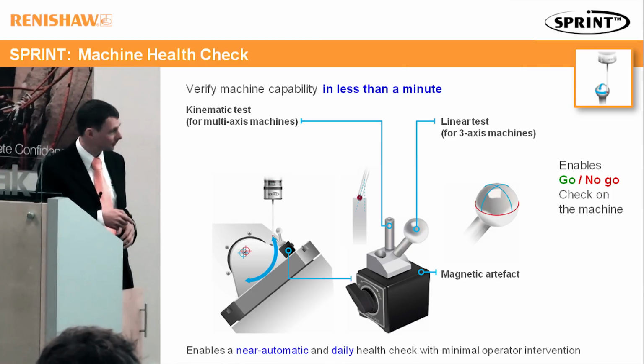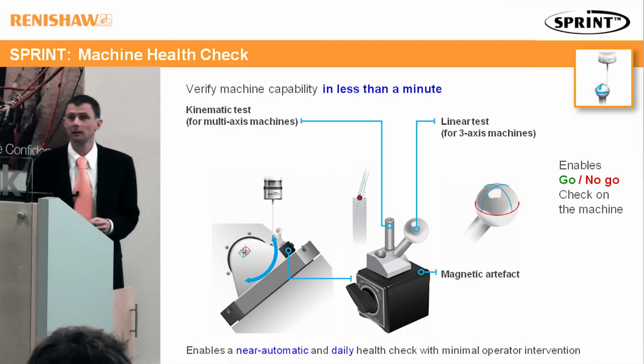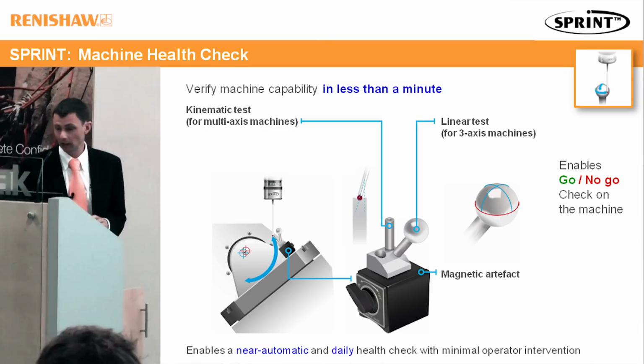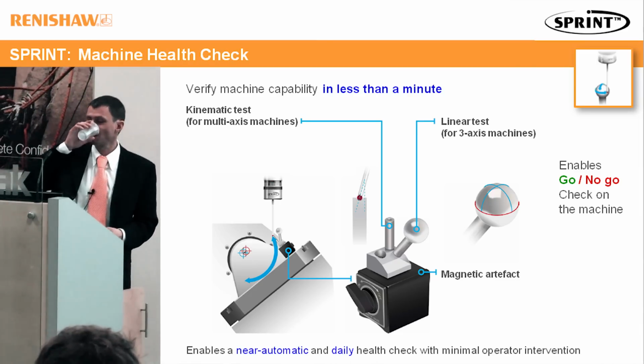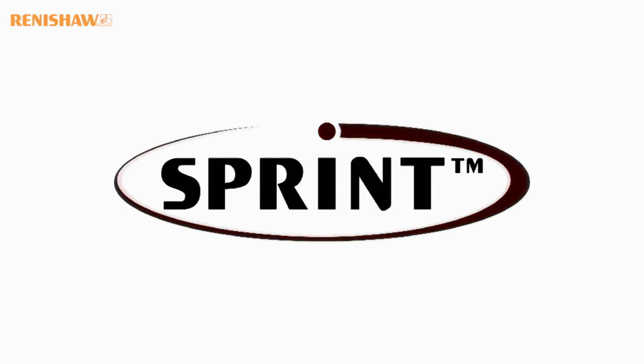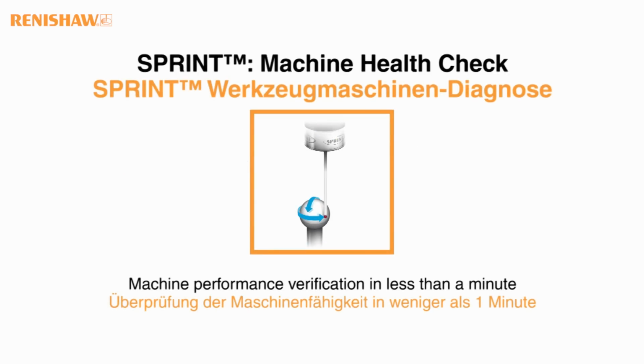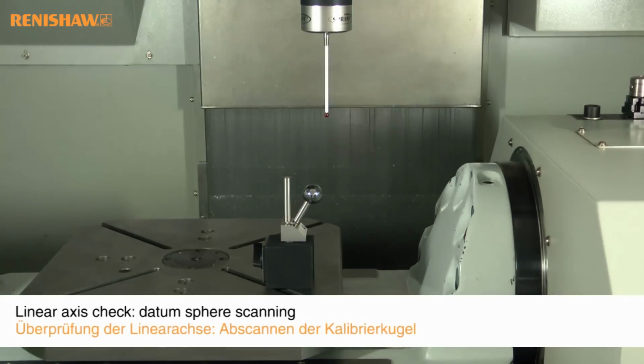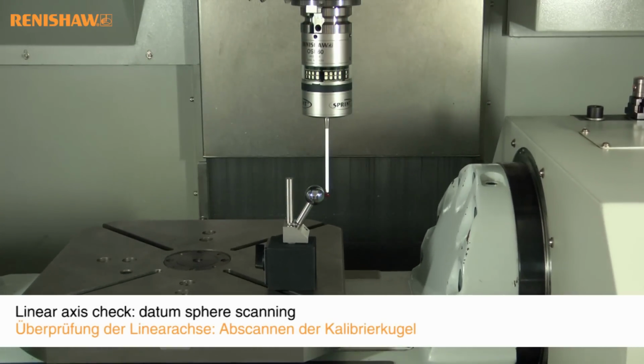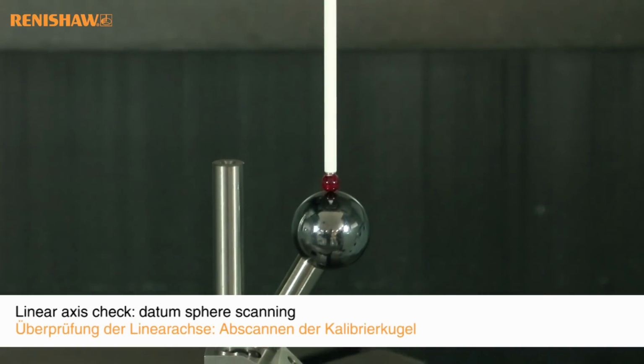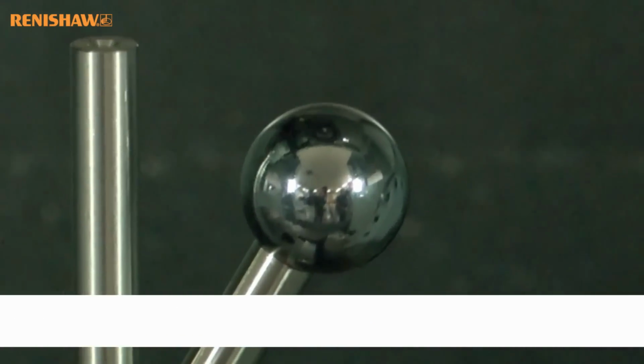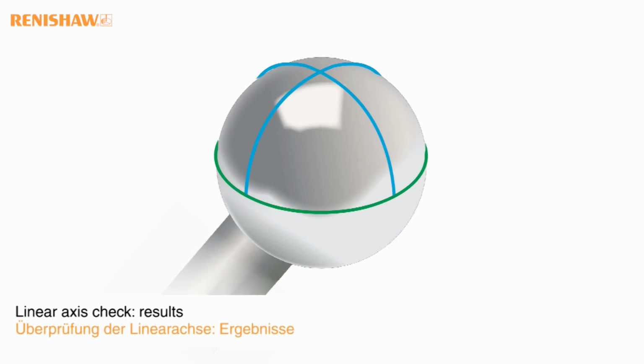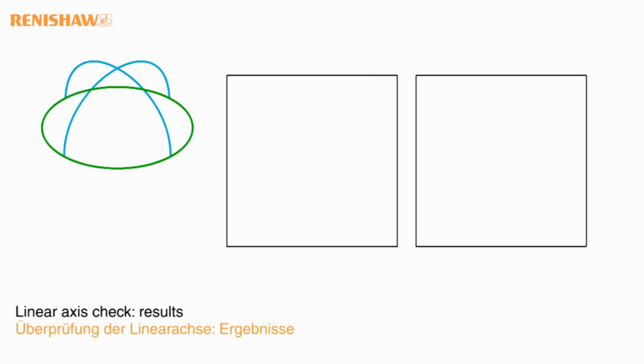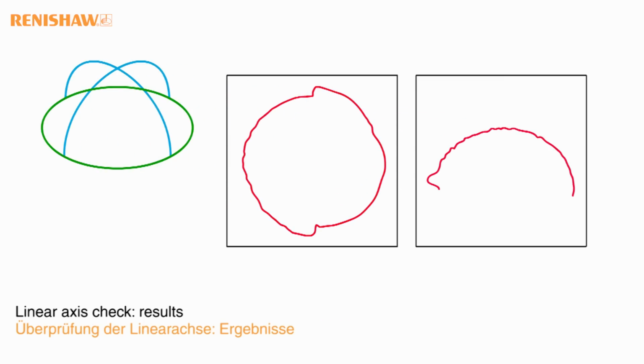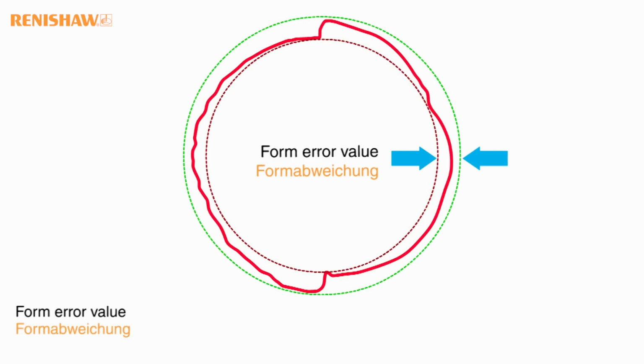The health check cycle can be set up to be near automatic and can provide a daily health check on your system to monitor machine capability over time. So starting with the 3-axis check on the sphere, the probe first locates the sphere, then it takes a series of profile measurements across the sphere. Obviously, we're collecting a lot of data, 1,000 points per second. We get a very good understanding of the form of the sphere, and we can use this form to generate a form error that can be output to the machine variables and used as a tolerance check prior to deciding whether to proceed to cutting a part.